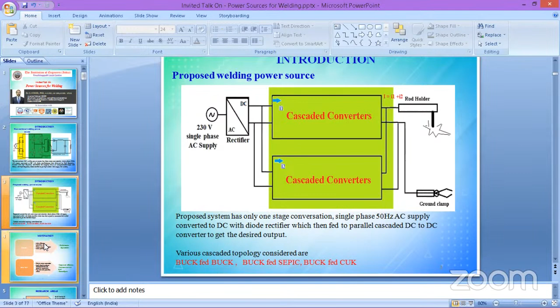So the solution is a single stage conversion, meaning only one-time AC to DC conversion, that's all. I will not go for AC, DC and all again - directly it is a single stage conversion. So less stress on the semiconductor by going for parallel mode, current sharing will be there, thereby stress on the semiconductor comes down and there is no skin or proximity effect.